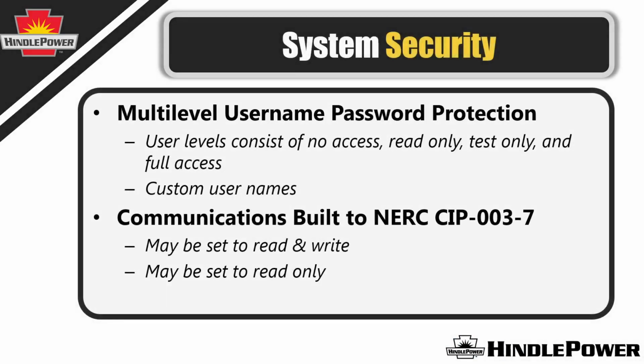Now, let's talk a little bit about security. So it's important to think a little bit about system security. You want to have a charger that has multi-level password protection, so that this way not anyone can just walk up and change controls. Also, you want to make sure that the communication system is actually built to NERC CIP-003-7. And it may be set to either read and write or may be set to read only. But these are now the current standards for the utility industry.